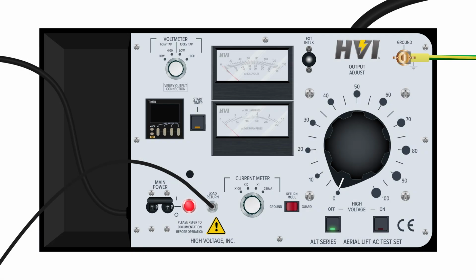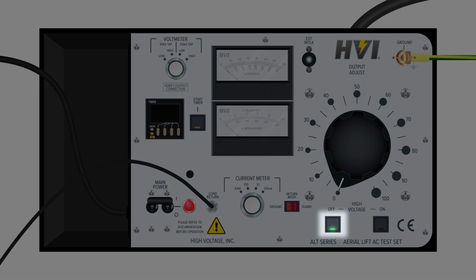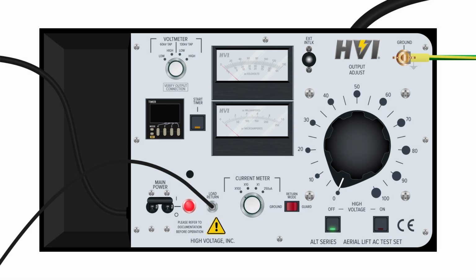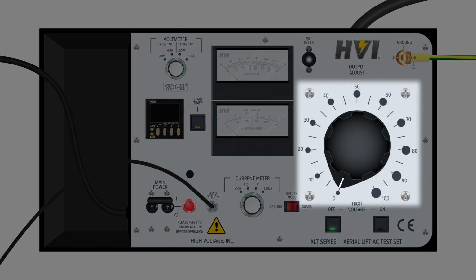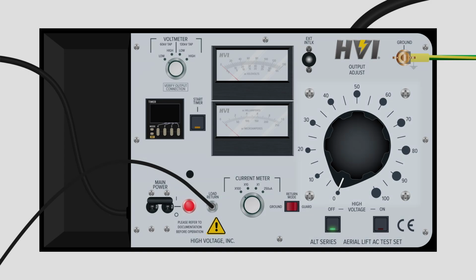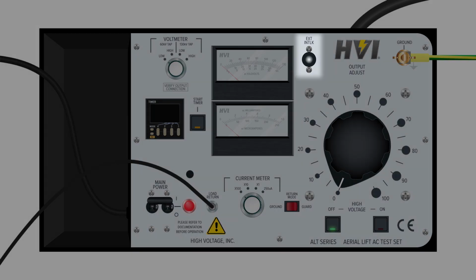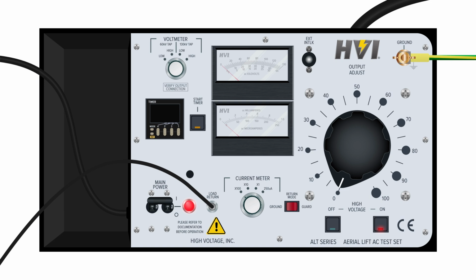The ALT series device will indicate the high voltage circuit is currently off by illuminating the high voltage circuit LED in green. Make sure the voltage output is dialed to 0. When the voltage output is set to 0 and the external interlock is in place, press the high voltage circuit on button. The high voltage circuit is now energized.